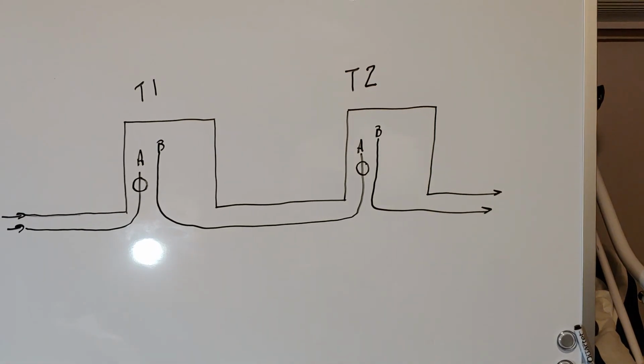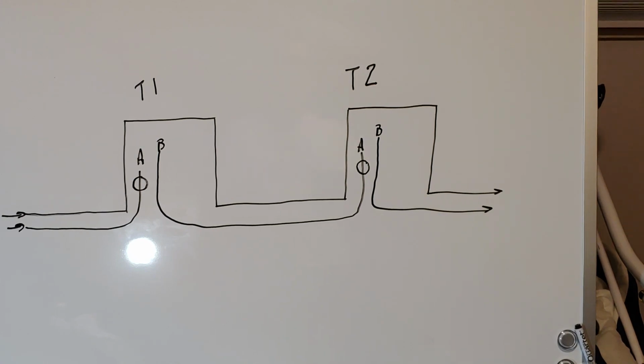Guys, this will serve as part 2 of the video on fault indicators, a continuation here with a little bit more in-depth explanation of how they work and something to look out for when you're out there using fault indicators. So on the screen I have here two transformers. You'll see the inbound cable on A, the circle designates a fault indicator, and the outbound cable on B. Then you'll see T2, the inbound primary cable on A, and the outbound primary cable on B.